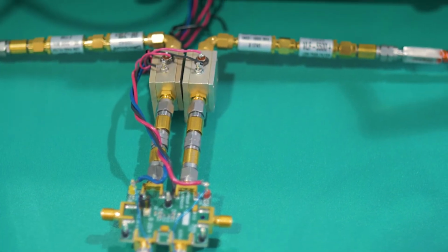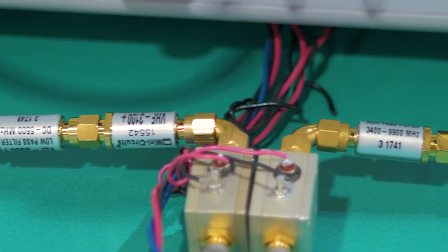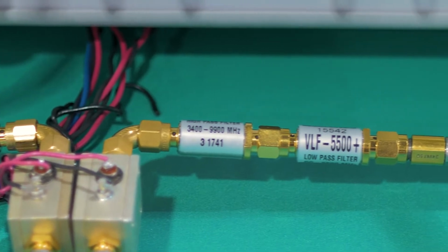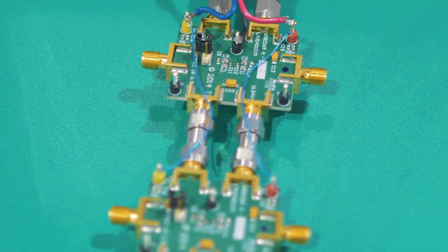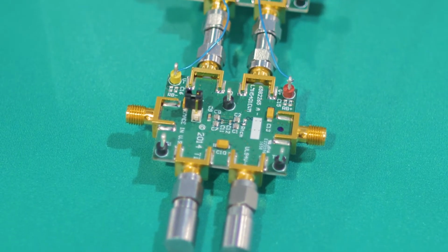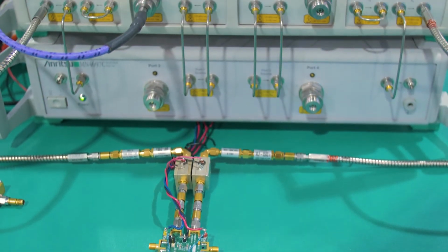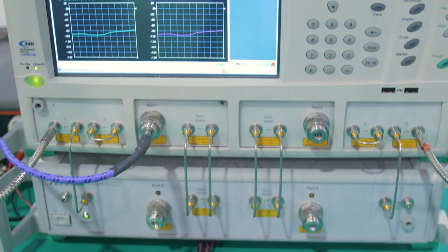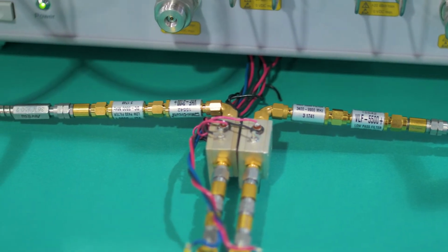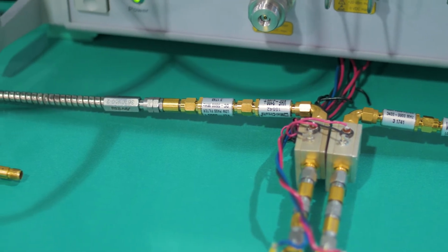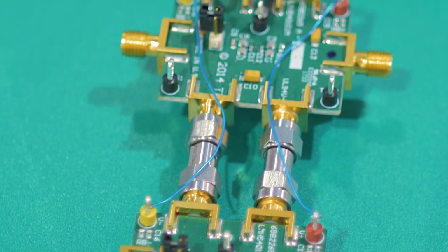Well, you've got a demo set up behind us. Why don't we go through that? On this VNA setup, we have a differential noise setup. Basically, we're measuring a DUT, an amplifier that has a differential noise figure or correlated noise figure across the paths. In today's current industry, we're doing single-ended measurements. We take a single-ended measurement of one path and a single-ended measurement of the other path for the noise figure measurements, and then we combine those paths in post-processing and calculate the differential noise figure.